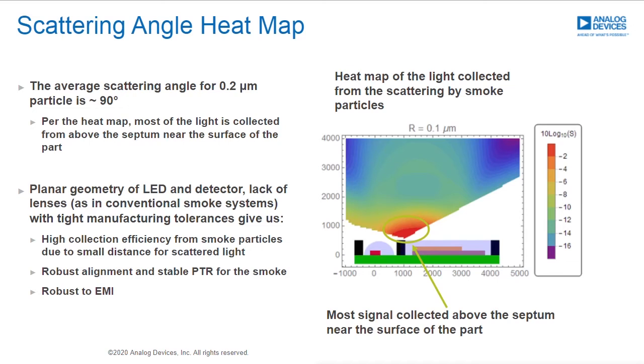This slide goes into a scattering angle heat map, which shows when the smoke enters the optical path, where most of that smoke is being detected. So as you can see here, we have a module, it's a really small form factor module. It's like 3.8 millimeters by 5 millimeters.